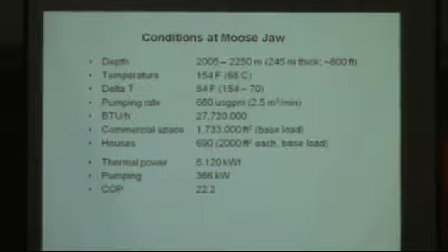So it needs a large footprint. It needs a large load to make it viable. Now, baseload refers to the amount of energy that is required on average. Like, say, the average temperature in Saskatchewan in January is -15. Well, this system would be designed to provide all the heating necessary to -15. And then for colder days, that heat would be supplemented by natural gas. So this wouldn't work in isolation. There'd still be gas. If it's a house, for example, there would still be a natural gas furnace working in conjunction with this. They would work together.